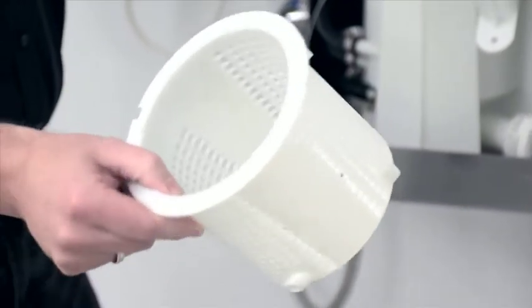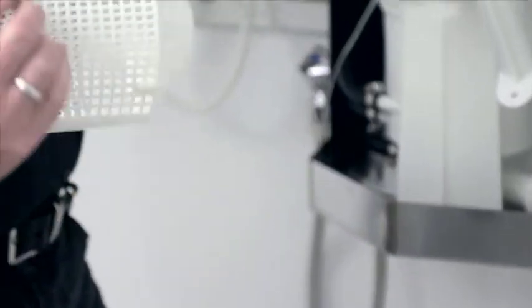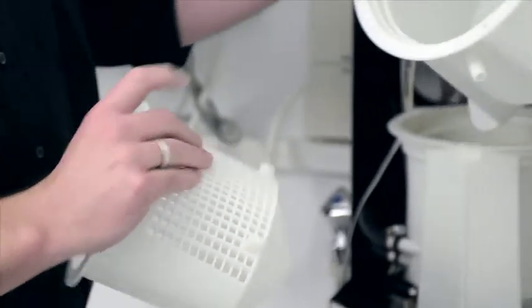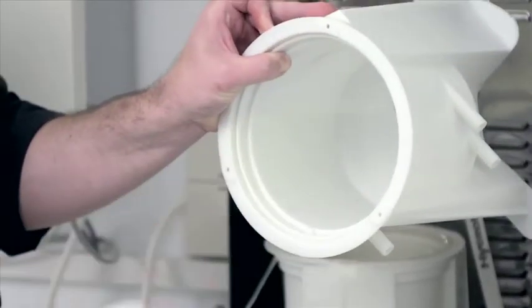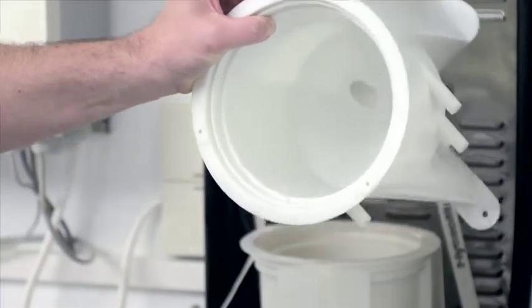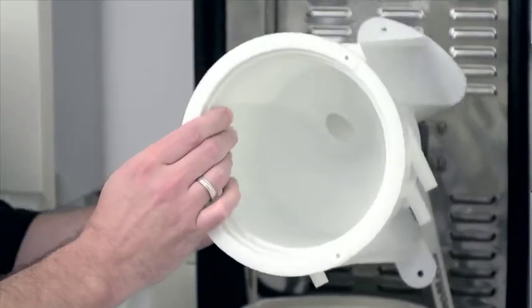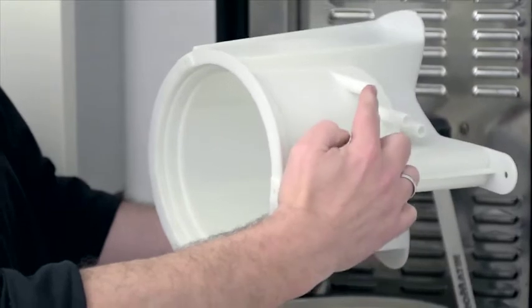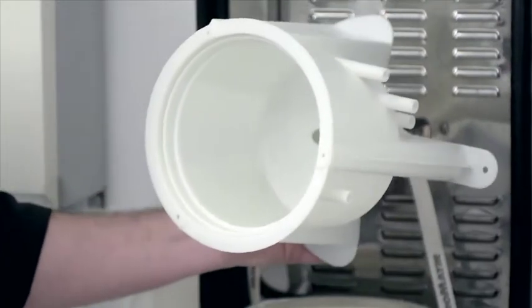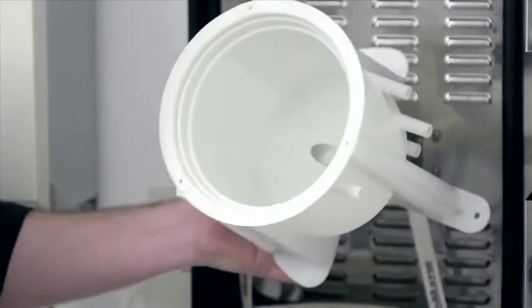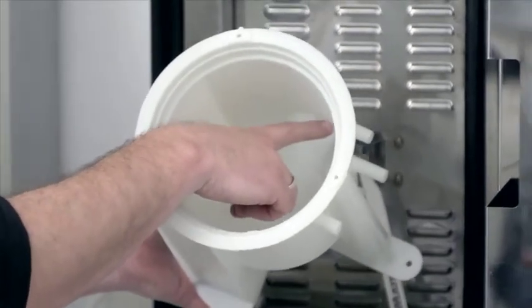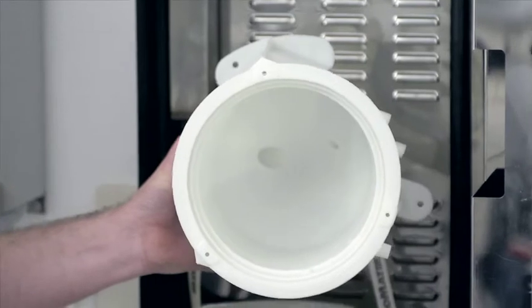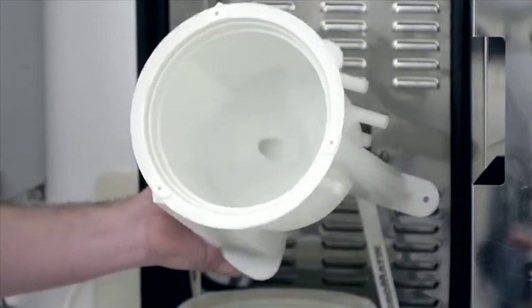When the unit has been running a certain time and calcium deposits have been produced, this will of course be filled with deposits and have some weight to it. That is why we have added the access holes. The strainer is cleaned from limescale deposits, emptied. These holes here, please clear them out. And then very important, the inner part of the base itself must be freed of calcium deposits. We have here these passes for the hose connections. Water flows into the cylinder there. And it is especially important that here on the inside, where the water exits, that these areas are thoroughly cleaned and the deposits get out of there.